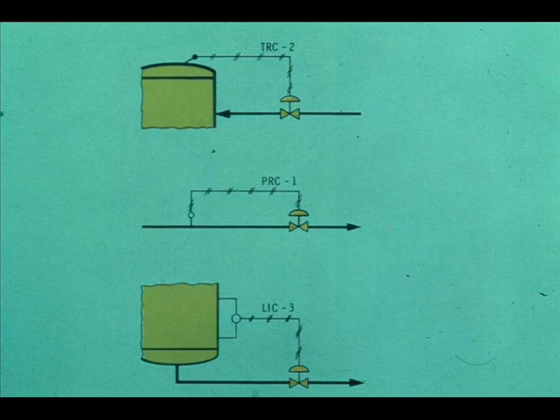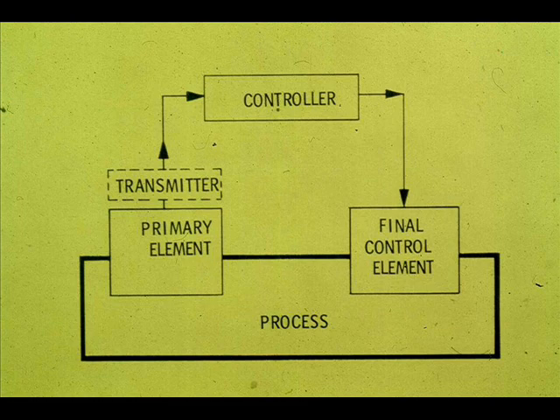Similar automatic control loop configurations could be drawn for the simplified control schemes for temperature, pressure, and level. But let's combine them all into a generalized block diagram. Here are the essential parts of an automatic control loop: the primary element, which measures the process variable; transmitter, if required; the controller; the final control element, which is usually a control valve; and the process being controlled. This general diagram can then be used to describe any automatic control loop.